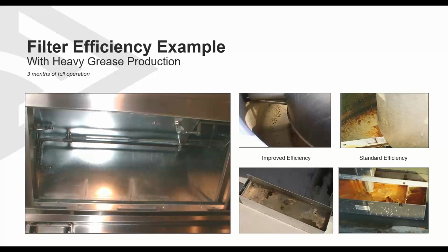Filter efficiency is shown here. If you have an improved filter, you can see that the grease buildup is reduced, and this is only in 3 months of full operation. So it doesn't take that long for grease to build up, especially if it's a heavily used hood with a lot of grease production underneath it. The kitchen is cooking burgers on an hourly basis, high level of burger production. So think about that. Depending on the kitchen application, there could be a lot of grease buildup.